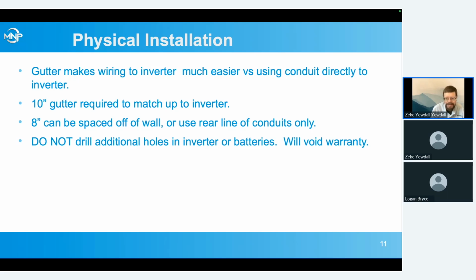We provide a template where you can punch all the holes to match up with the inverter, and just mate it right up to the bottom of the inverter. A 10-inch gutter mates up very well to the bottom of the inverter and comes just about to the front of the inverter. An 8-inch gutter can either be spaced off the wall a little bit with, say, a single piece of strut, or you can bolt it to the wall and only use the rear line of conduits on the bottom of the inverter instead of both lines. That depends on how much you have coming in and out of the inverter.